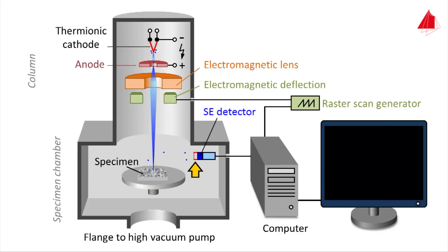To generate a magnified image of the sample, the raster scan generator directs the electron beam to the left rear part of the sample and stops there for a short time. The number of secondary electrons is recorded in the SE detector, the signal is amplified, and displayed as a dot at the top-left corner of the monitor. The electron beam then pans slightly to the right, stops again, and the measurement is repeated. The principle is: many recorded secondary electrons lead to a bright image point, few electrons lead to a gray image point, and none at all to a black one. An entire row is covered this way, then a second row, until finally a rectangular area has been scanned and an image appears on the monitor.